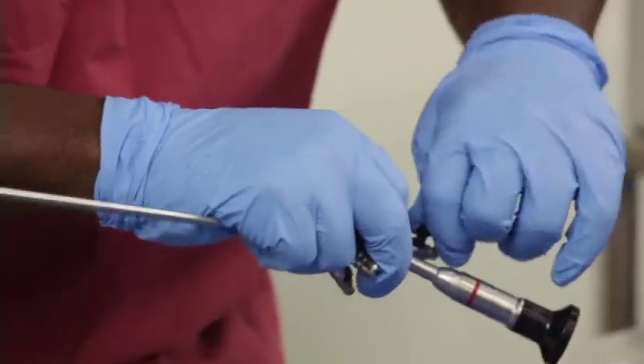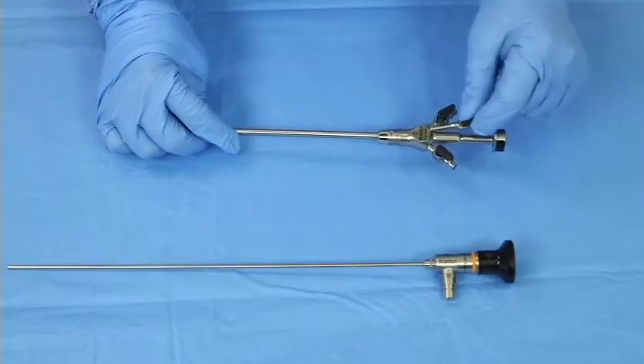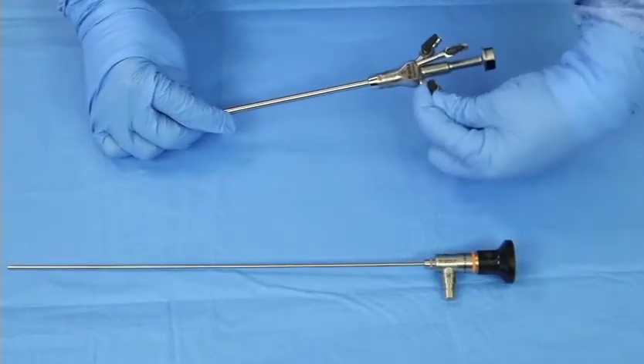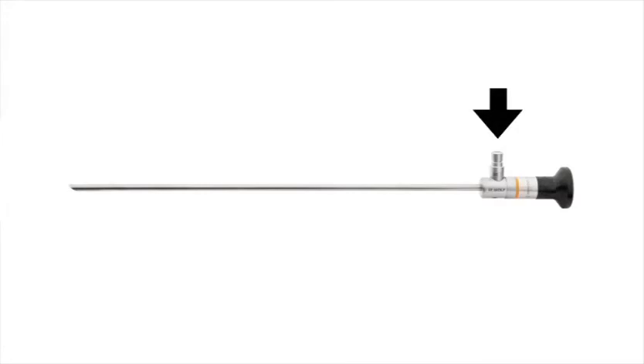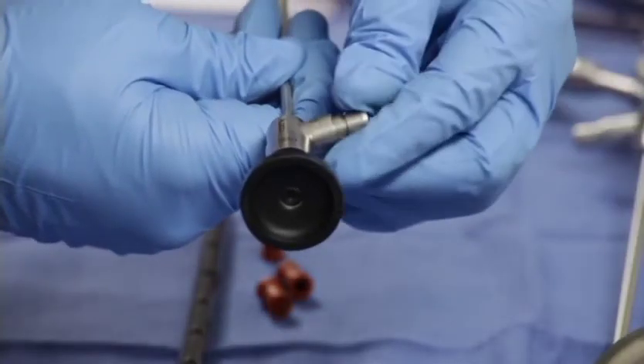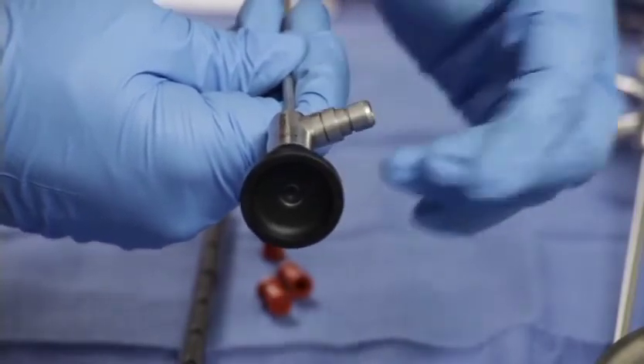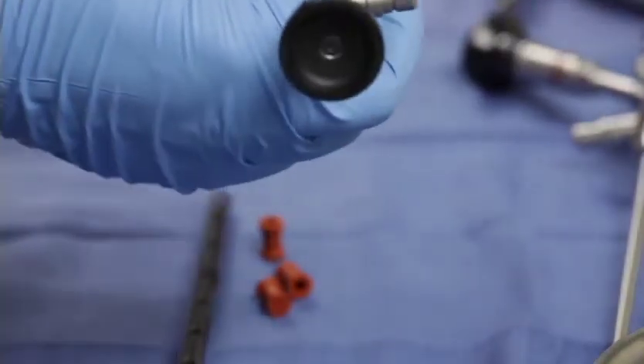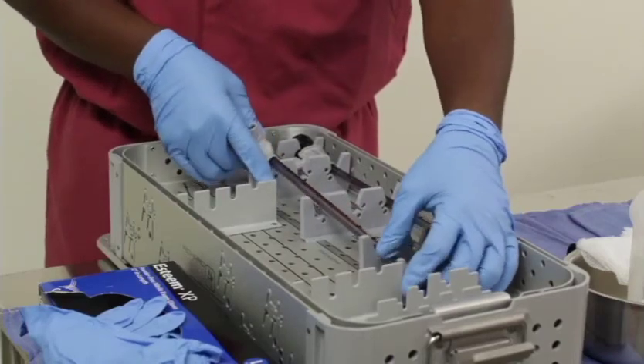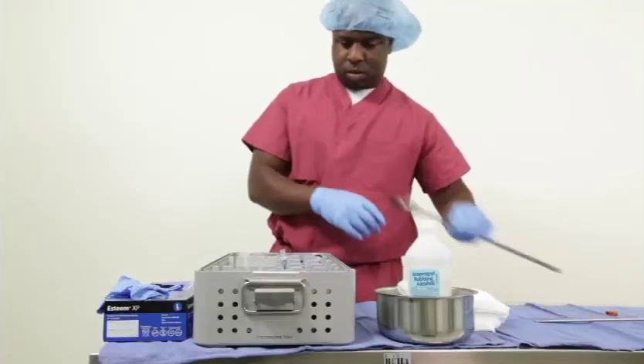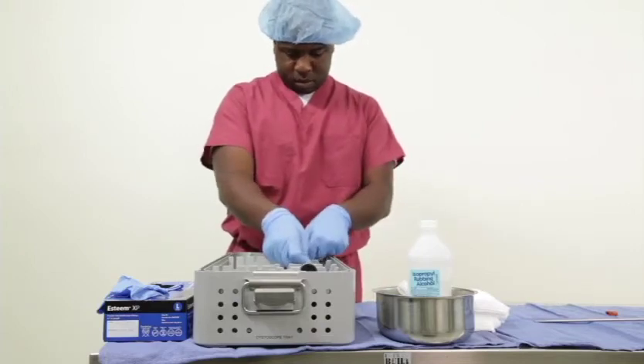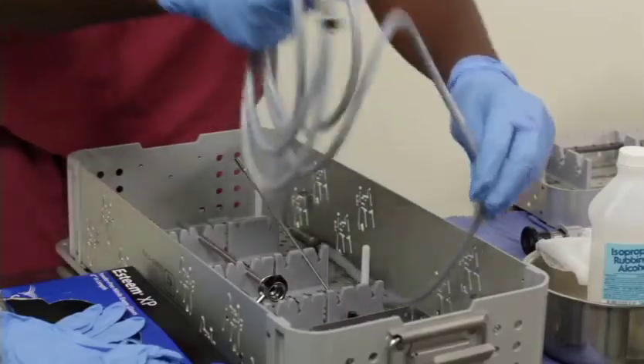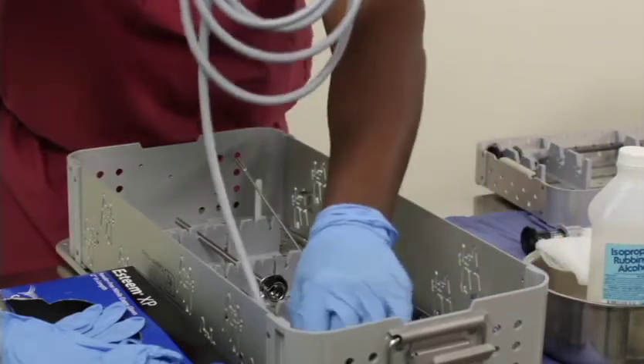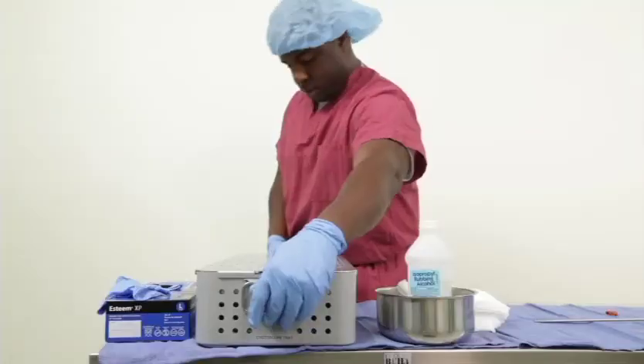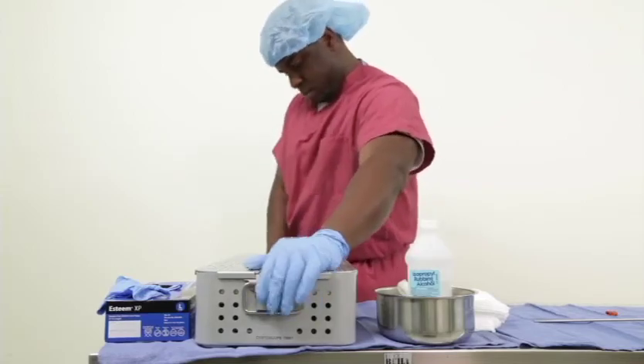Be sure to check the manufacturer's instruction manual before reattaching any seals, gaskets, or caps to ensure they can be assembled onto the scope before sterilization. The light post adapter can be reattached for sterilization. Turn the adapter 1 1/2 turns onto the light post so it is slightly loose to allow for effective sterilization. Richard Wolf scope protectors are validated for sterilization. Protect the endoscope and keep it separated from the other instruments in the tray. Instrument trays made specifically for endoscopes and instruments also help separate and protect the endoscopes from damage. The endoscope is now ready for terminal sterilization.